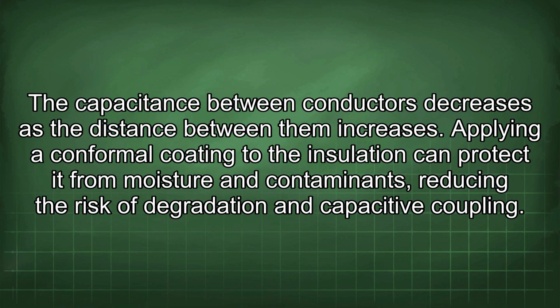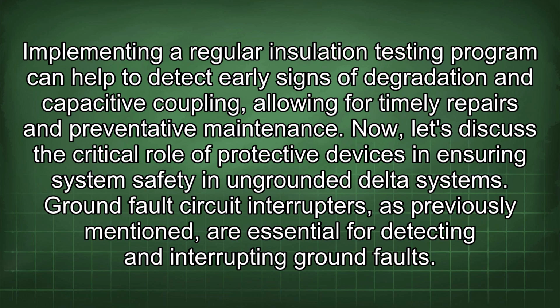Applying a conformal coating to the insulation can protect it from moisture and contaminants, reducing the risk of degradation and capacitive coupling. Implementing a regular insulation testing program can help to detect early signs of degradation and capacitive coupling, allowing for timely repairs and preventative maintenance.